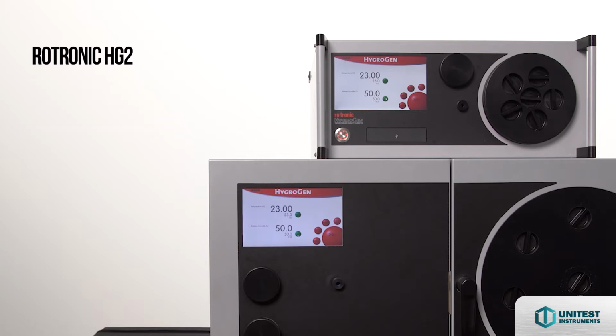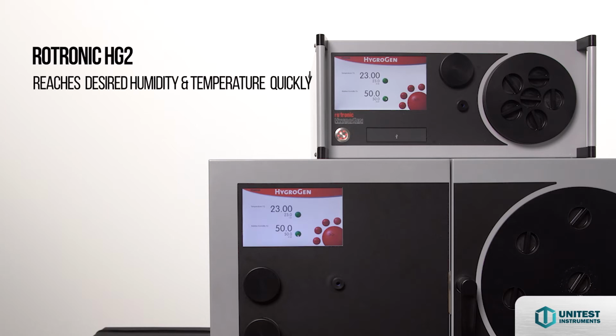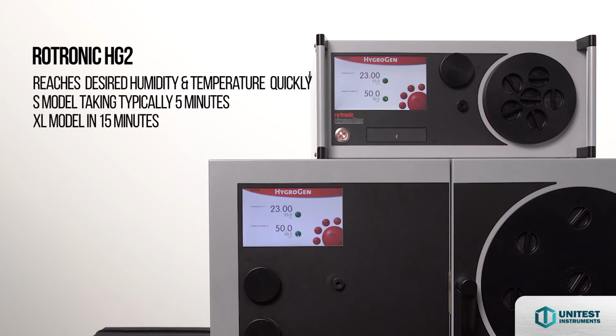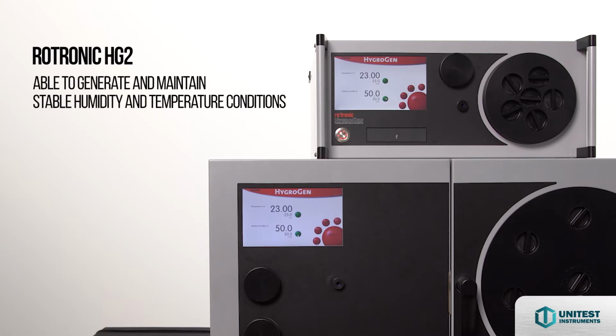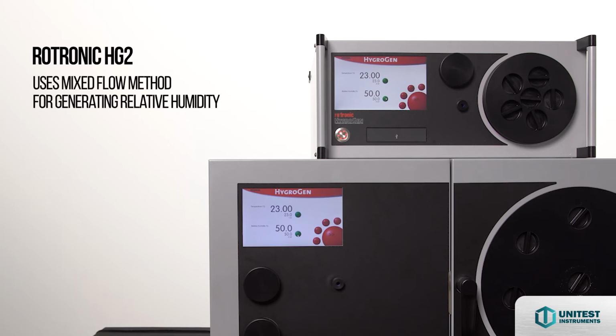The HG2 is able to reach its desired humidity and temperature settings quickly, with the S model typically taking 5 minutes and the XL model taking 15 minutes. The HG2 is also able to generate and maintain stable humidity and temperature conditions, with ±0.1% RH and ±0.01 degrees Celsius. The HygroGen2 uses a mixed flow method for generating the relative humidity required by the user.